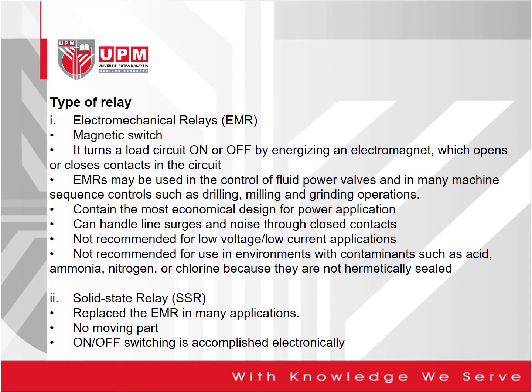And then here, types of relay. As you can see here, we have two types being introduced, EMR and also the SSR. What is EMR? Electromechanical relay is a magnetic switch. It turns a load circuit on or off by energizing an electromagnet, which opens or closes contacts in the circuit. So EMRs may be used in the control of fluid power valves and in many machine sequence controls such as drilling, milling, and grinding operations.